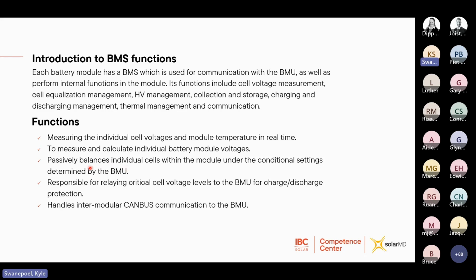The BMS has resistors on the left side of the BMS, which will passively balance the cells when it is in the balancing range. So the batteries are set for top balancing, so they will balance when the battery is full, and it will balance when the current is low. So it will generally be in the floating stage of the operation. That's when it will balance, if the cells are above the delta, which is required to balance. And then because it's recording the cell voltage and module temperature, it needs to relay the critical information to the BMU so that the BMU can then calculate the charge and discharge protection.